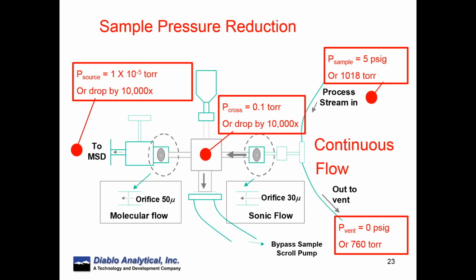So if we look at the interface that I showed earlier, let's take a view as to how the sample flows through the system. You can see the process stream in the upper right, going down to the vent. That's potentially a large flow, possibly 100 mils a minute, liters per minute, whatever it might be, and it's just flowing past the analyzer. The analyzer then, with the bypass scroll pump, draws in a few mils per minute across the first orifice, and it drops down to a tenth of a torr from 5 psi, from 100 psi, whatever it might be in your process.